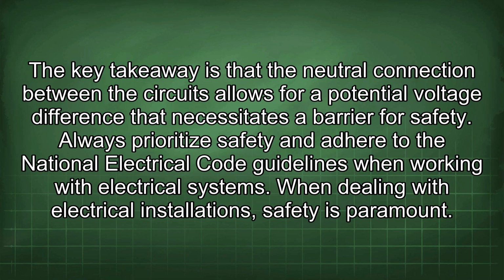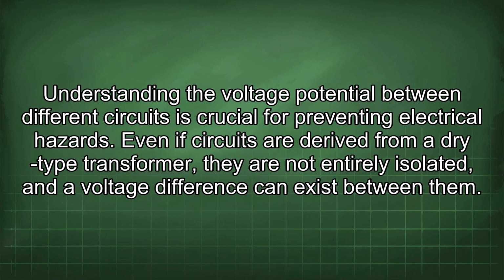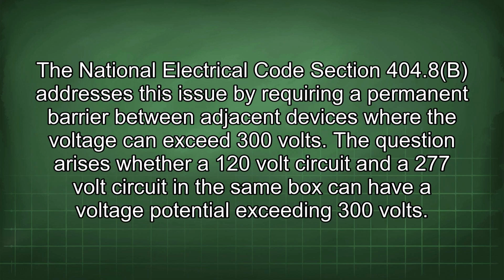When dealing with electrical installations, safety is paramount. Understanding the voltage potential between different circuits is crucial for preventing electrical hazards. Even if circuits are derived from a dry-type transformer, they are not entirely isolated, and a voltage difference can exist between them. The National Electrical Code section 404.8(B) addresses this issue by requiring a permanent barrier between adjacent devices where the voltage can exceed 300 volts.